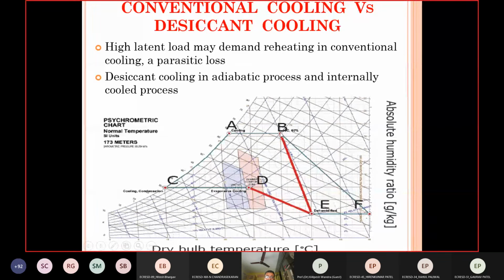Okay. One of the advantages of desiccant cooling as shown here is that if your latent load is high, in that case with a conventional system you may have to go like this, right? And this shows reheating. Okay. While in case of desiccant cooling, if you provide cooling along with dehumidification, then you may follow this path on the psychrometric chart, and then the evaporative cooling may take you to the comfort zone.